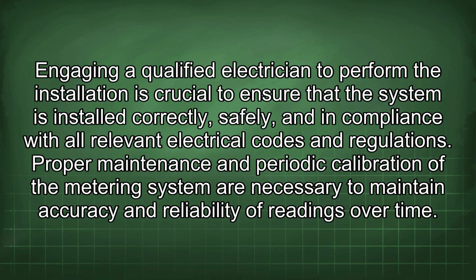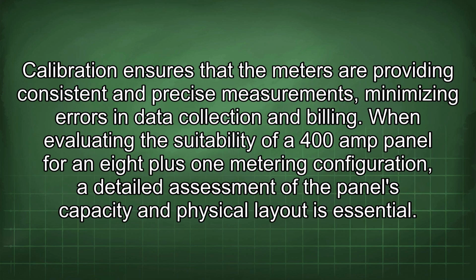Proper maintenance and periodic calibration of the metering system are necessary to maintain accuracy and reliability of readings over time. Calibration ensures that the meters are providing consistent and precise measurements, minimizing errors in data collection and billing. When evaluating the suitability of a 400 amp panel for an 8+1 metering configuration, a detailed assessment of the panel's capacity and physical layout is essential.